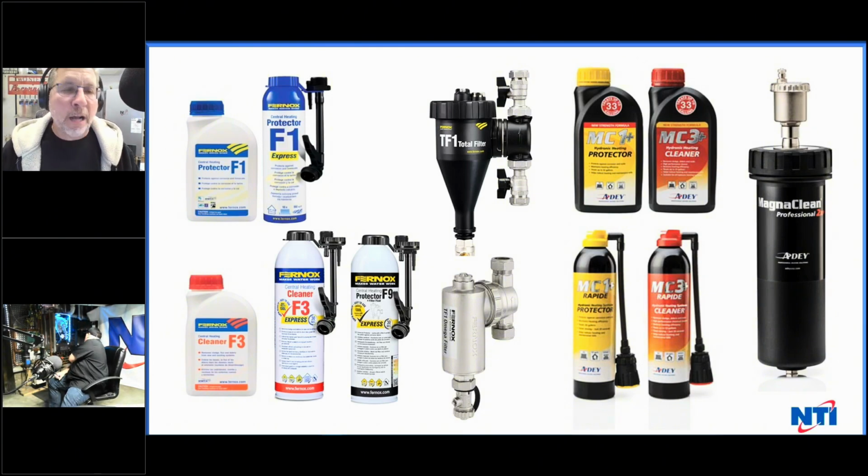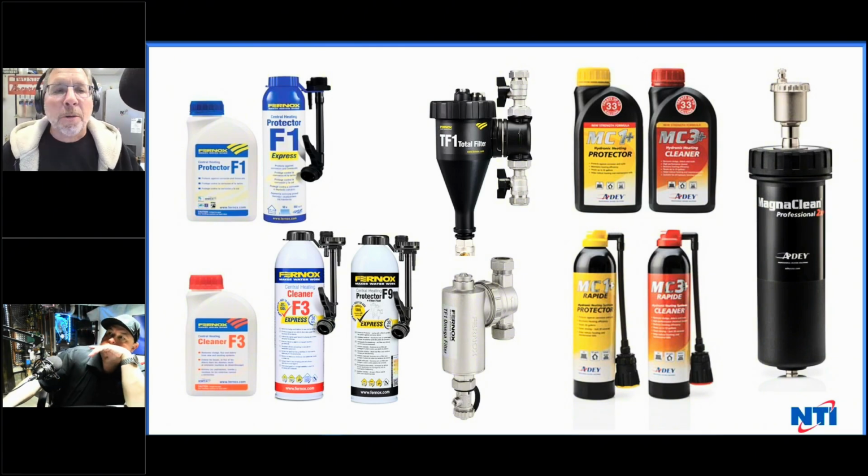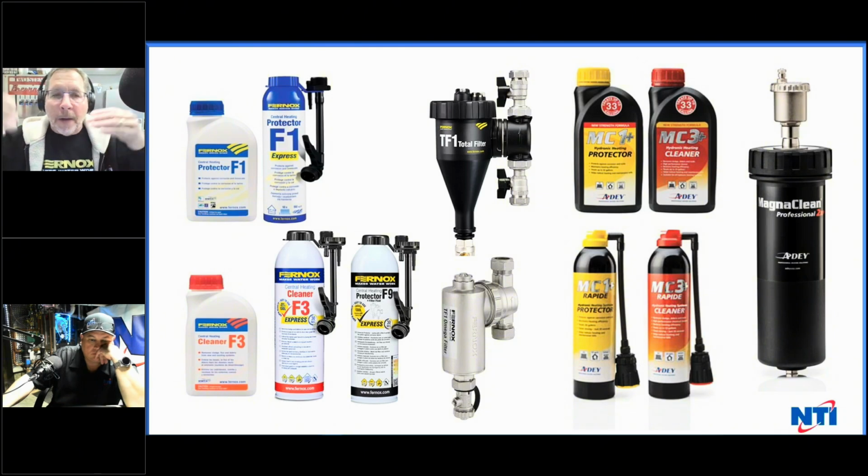Now, the question comes to me all the time: hey, Wheels, what happens if we're replacing the boiler because the boiler bottom blew out and we have to put a new boiler in? What do we do then? Well, then you put a magnetic filter on the return and use the protector F9, Fernox F9. It's a new product out. It actually has two-thirds F1 and one-third F3 in it. So it'll emulsify and get all that crap up in a slow way while it's protecting the system, and bring it all back to the magnet.